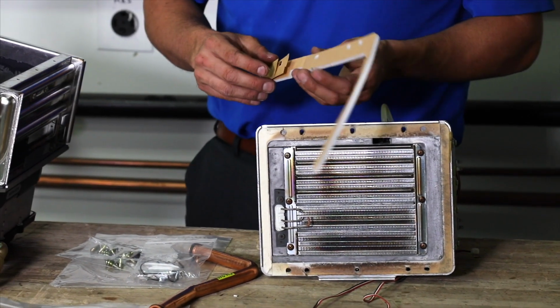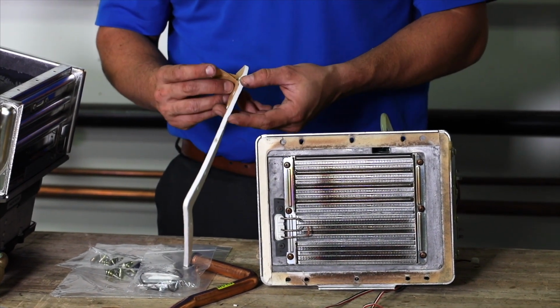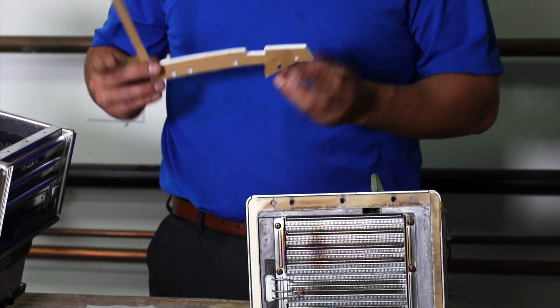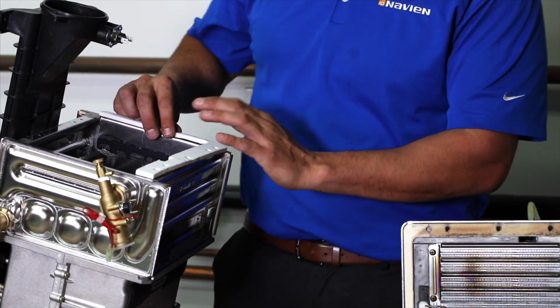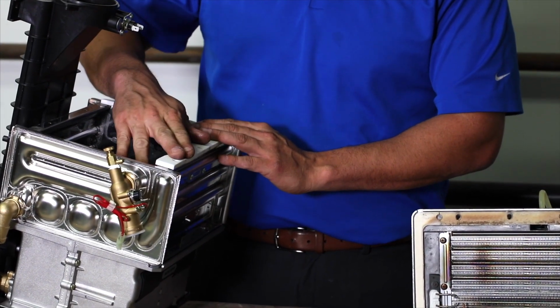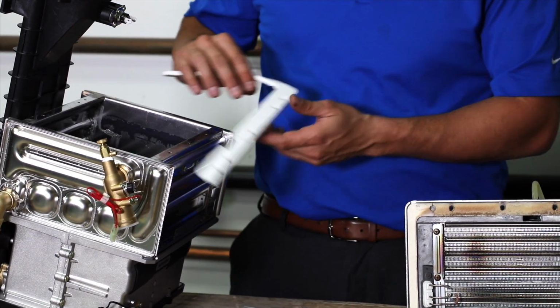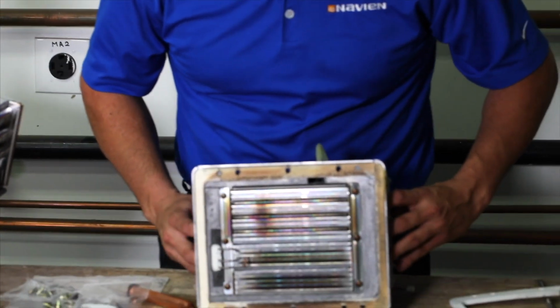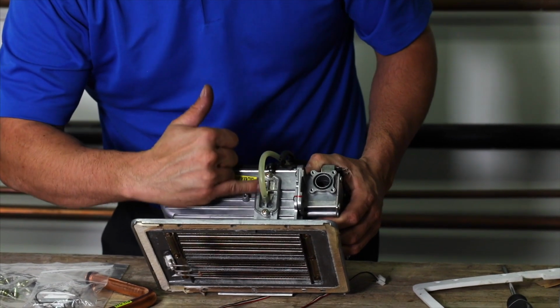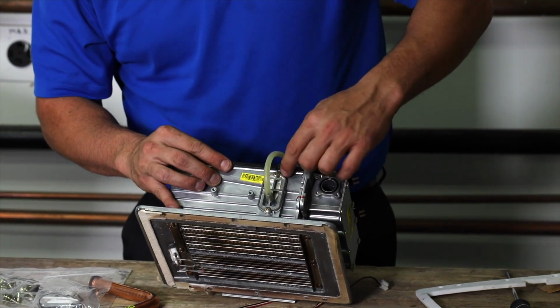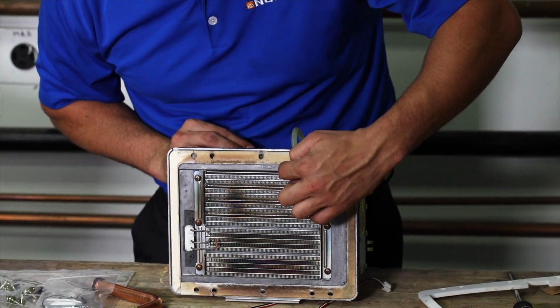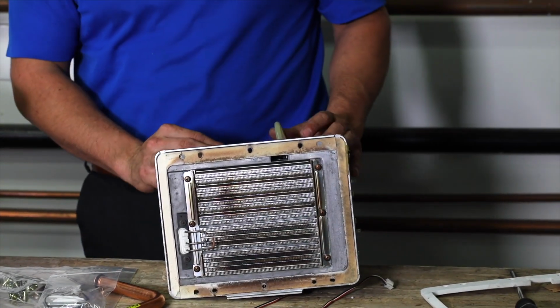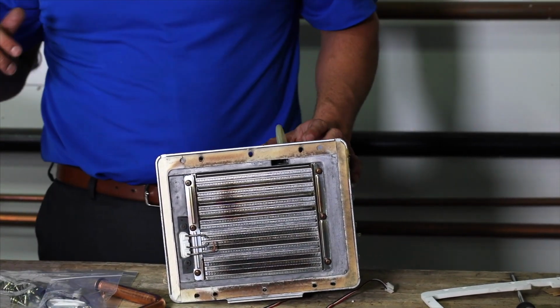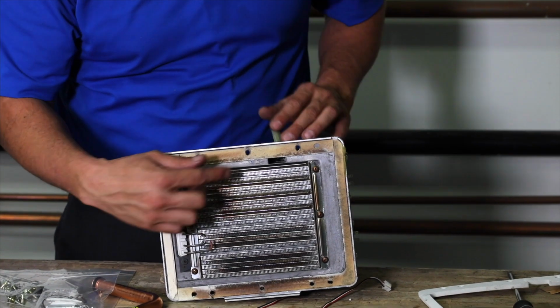And very important to note is, it has a sticky side to it, and you absolutely positively do not want to attach your seals to the heat exchanger. The reason for that is on your burner, as you can see here, this venturi, or this little cutout, is very important to the operation or the combustion side. So the air coming through here is going to come out through here.